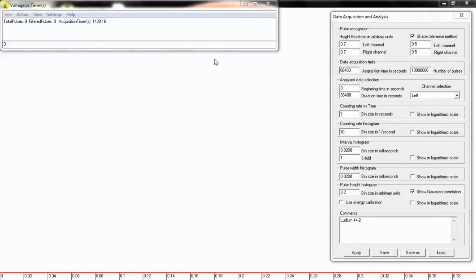So here we are in PRA, and I have the height threshold in arbitrary units set to 0.7. Typically, I try to keep this pretty close to the resolution of the detector. But anyway, 0.5, 0.6, 0.7, 0.8, and 0.9 seem to be pretty good for most detectors, and you might want to play around with these settings to get it right for your detector. But basically, I'm telling the unit the highest peak I want to look for, and the peaks come from the sound. Let me show you.